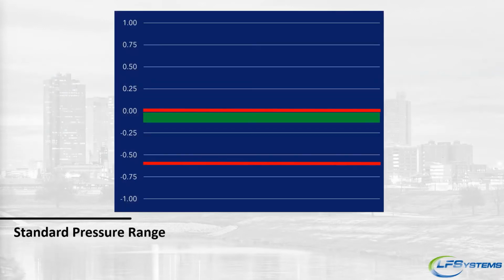And go back to the pressure thing real quick. The reason why we bring that up is a lot of controls that are out there only read negative pressure. So they read from 0 to 0.6. And the problem with that is that if your set point on a shaft, you want to maintain as close to neutral, or a very, very slight negative. You don't need to have a deep negative coming through that entire shaft. So if you set that for a 1/10 of an inch or 1/4 of an inch, to get you back into that middle, you're going to be pulling a lot of excess air out.